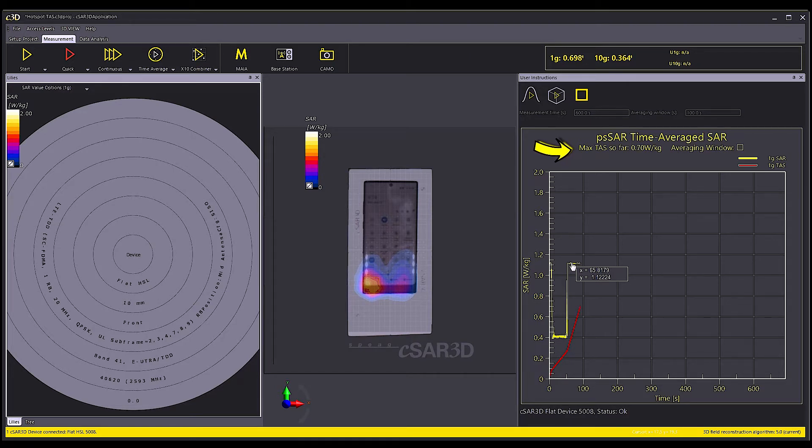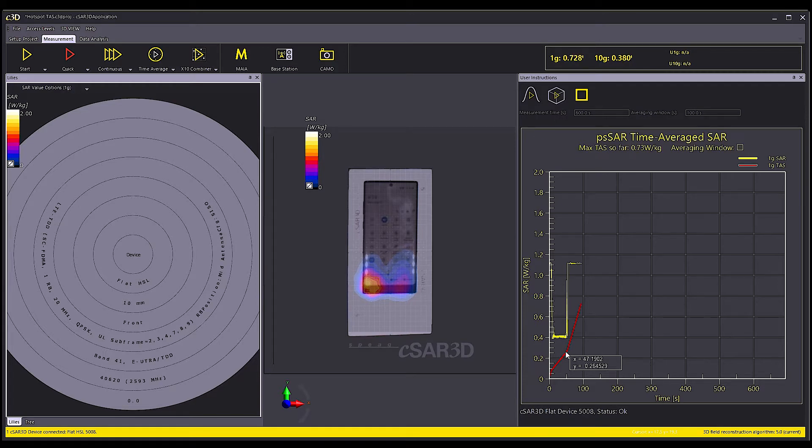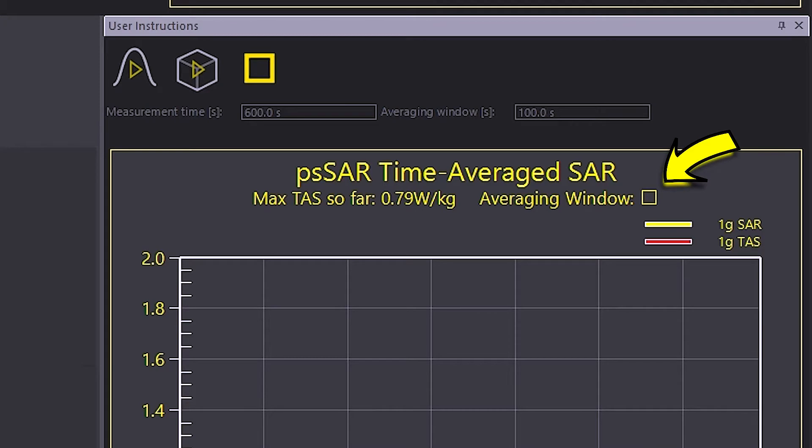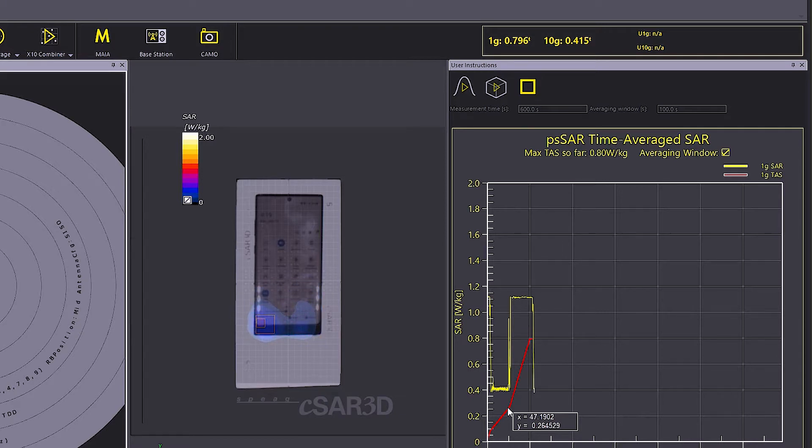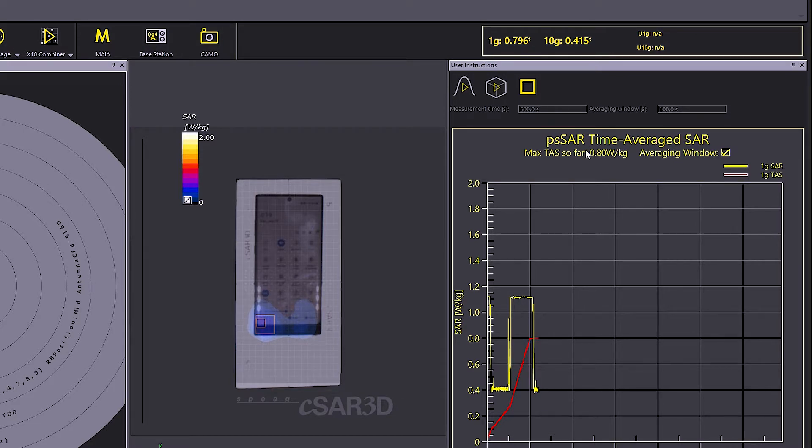As the averaging window length is 100 seconds, we see meaningful values of TAS after 100 seconds. We can see that after 100 seconds, the TAS value converges to a certain level. The device power control algorithm neatly maintains the time average SAR within this limit. I will now accelerate the video.